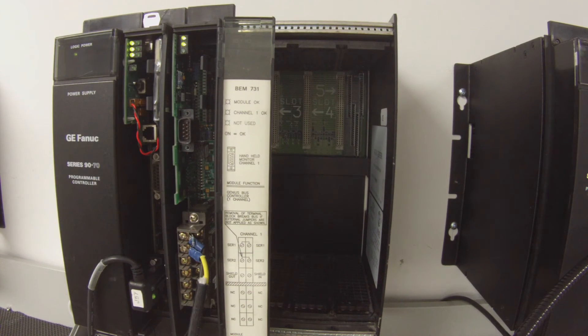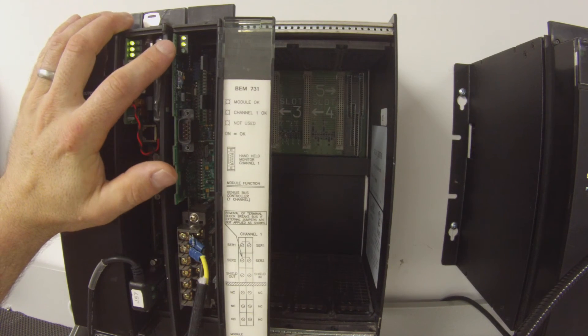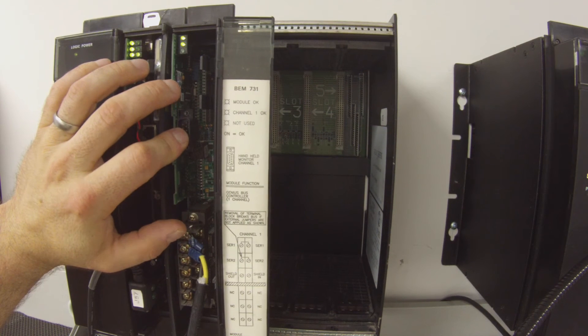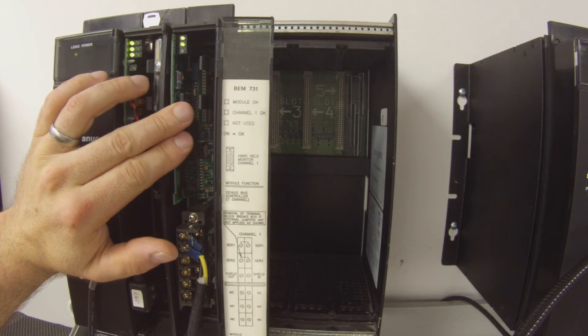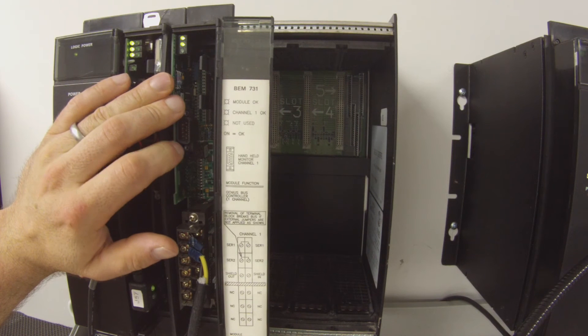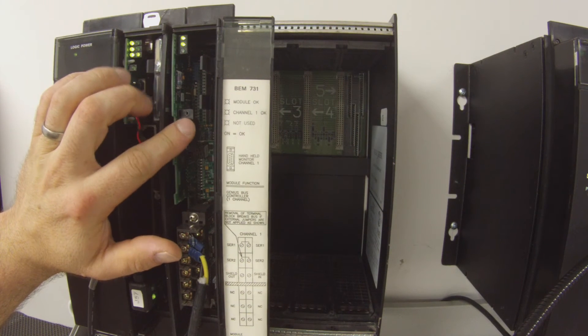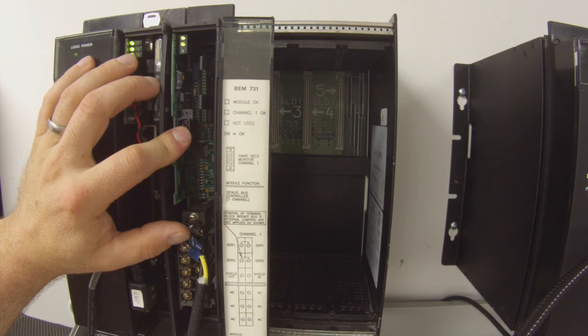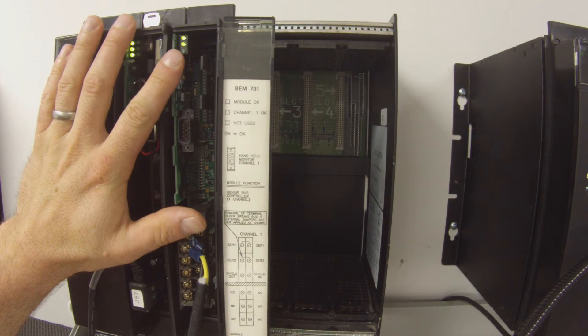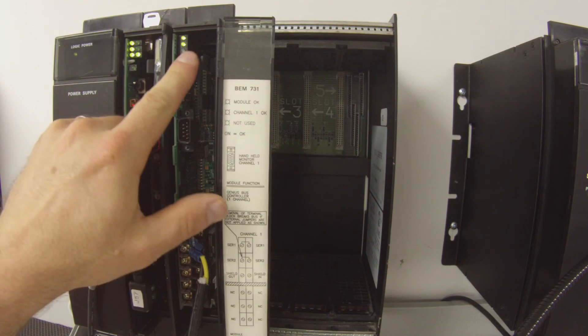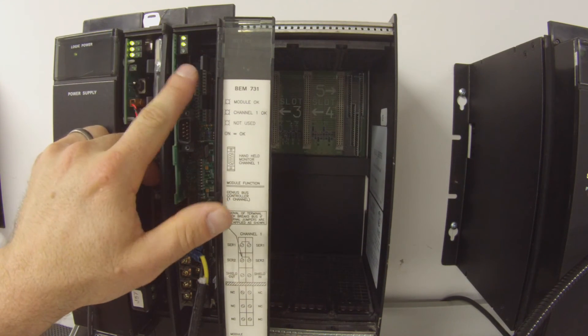So actually, I'll back up a bit. If the BEM 731, if you put it in and you don't get a module OK light, then there's definitely something wrong with this device. And this is something that we do look at and repair. We offer exchange programs, new and remanufactured products. So if it's something that you do need, please see us at PDFsupply.com. And of course, if the light's not working, you won't be able to follow the test thoroughly. So this is, in fact, a working device. And I do have both lights on now that it's in run mode.